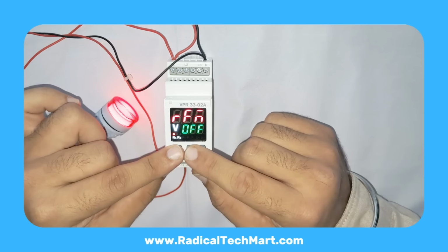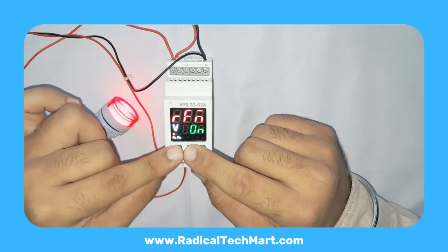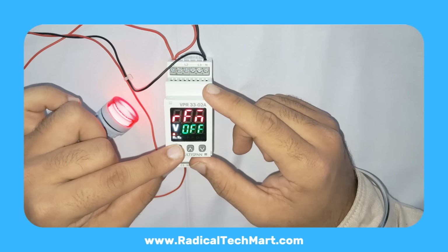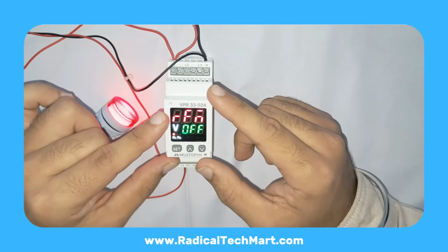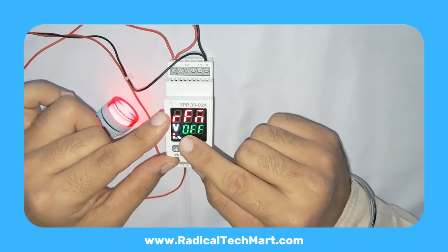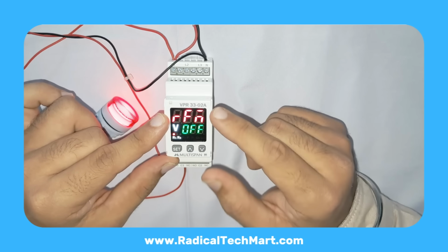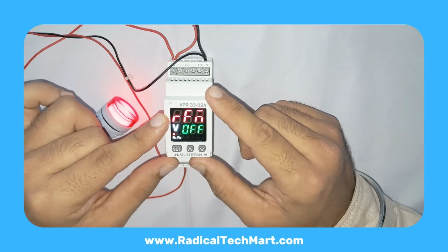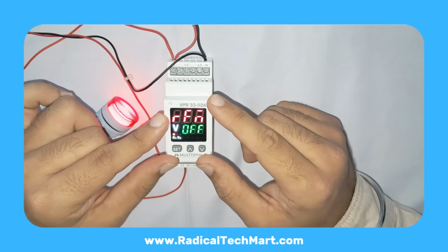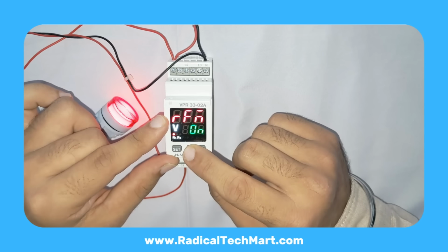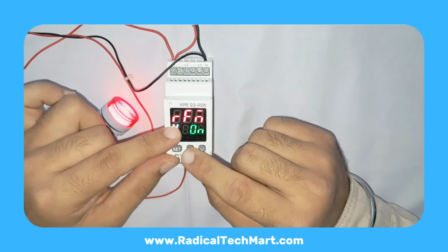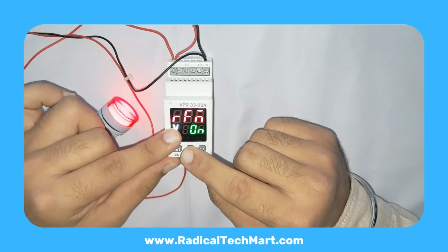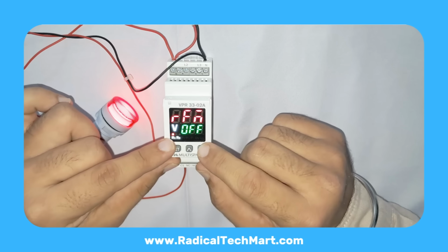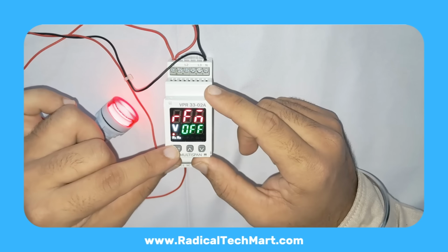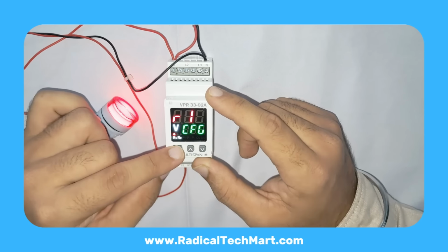This decides what the relay should do during a fault. Options are usually off, relay turns off during fault. On, relay remains on during fault. This is useful depending on your application. If the relay output is driving an MCCB shunt trip, you might want relay on in fault to trip the breaker. If it's just controlling a contactor, you might want the relay to switch off during a fault. Choose as per application, then press Set.